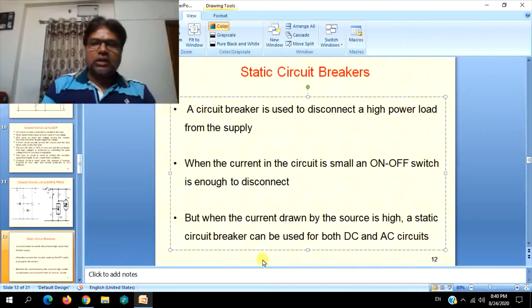Here is the circuit of a static DC circuit breaker, which is a simple example of what we discussed in our older sessions, where we discussed Class C commutation of thyristors or SCRs, or auxiliary commutation. The same circuit is used here, where the DC supply is given to the load and current flows through the load when and only when the main thyristor, indicated as TH, conducts. The other thyristor THA is used to turn off the main thyristor forcefully. That is why it is the auxiliary thyristor. As it is a DC circuit breaker, a forced commutation method has to be used, and in this circuit the auxiliary commutation procedure is followed.